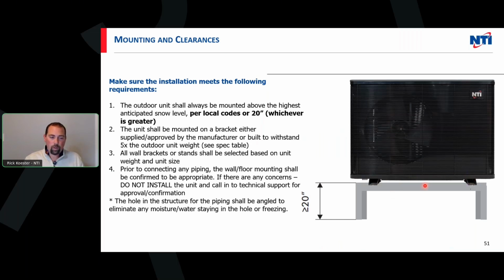If it doesn't, and it pools up underneath the machine or gets stuck inside because it's all clogged up underneath there, it's going to refreeze again. When it refreezes around the coil, and there are copper U-bends on the outdoor heat exchanger, there is that opportunity where it will contract over it, and it's going to split the U-bend. So the copper can get crushed because of the ice. Now we're going to lose our refrigerant, and we're going to have bigger issues in the system. So it's very important to make sure these things are off the ground, not just for airflow, but for drainage. We want to make sure all that water can get out during those defrost cycles.